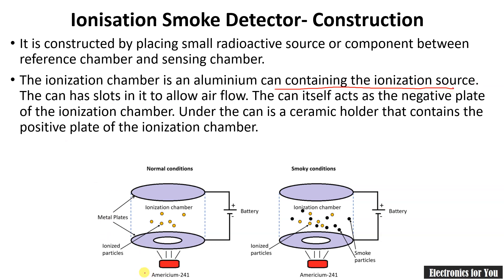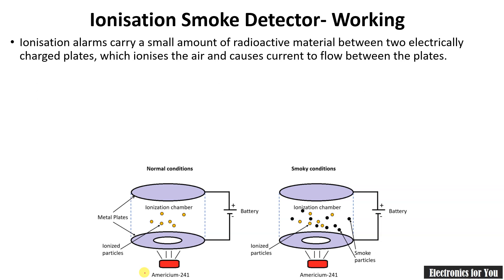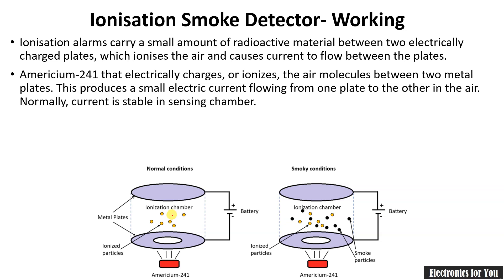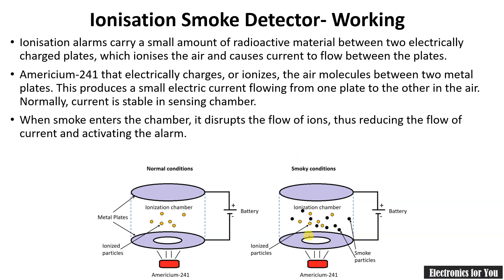A material known as Americium-241 is placed between the ionization chamber plates. In normal conditions, this ionizes the particles between the two plates, so a small amount of current flows between them. When a smoky condition is detected — shown as black dots representing smoke particles — the current between the two plates decreases. This change is sensed by the sensor, and the variation in current is used to detect smoke particles, thus activating the alarm.